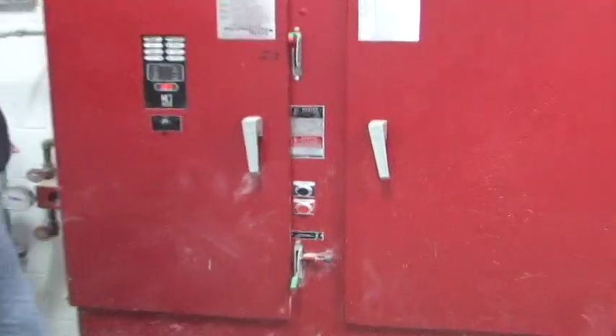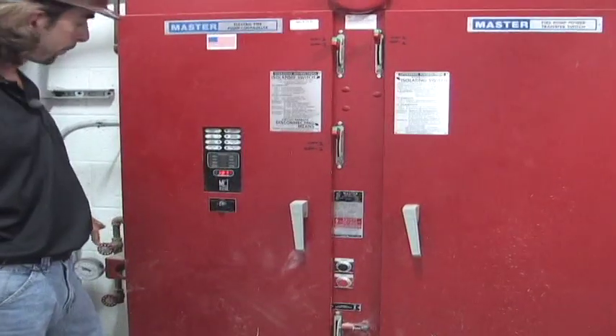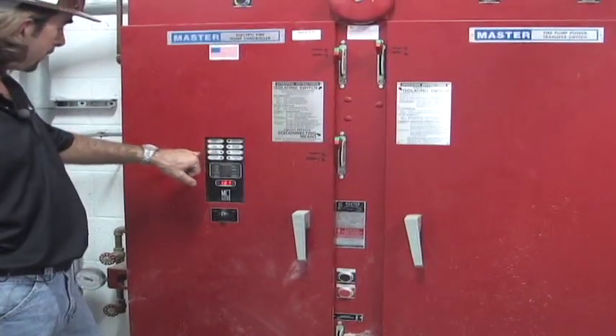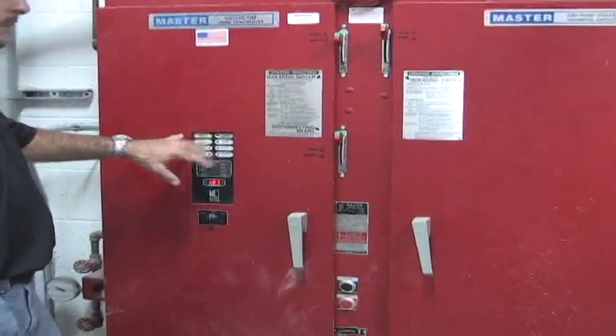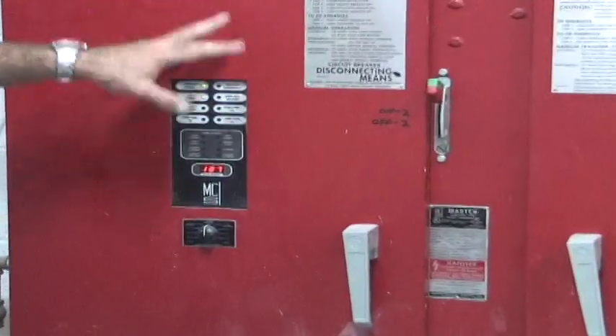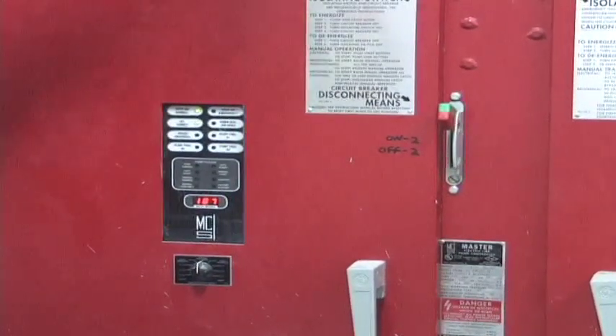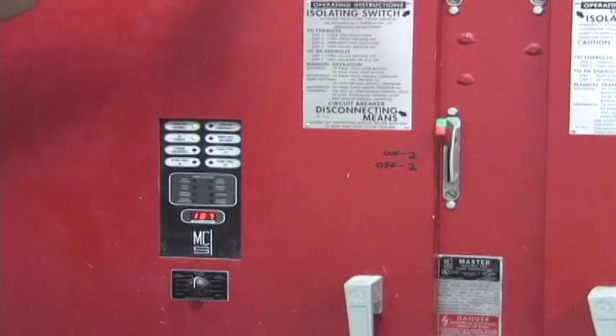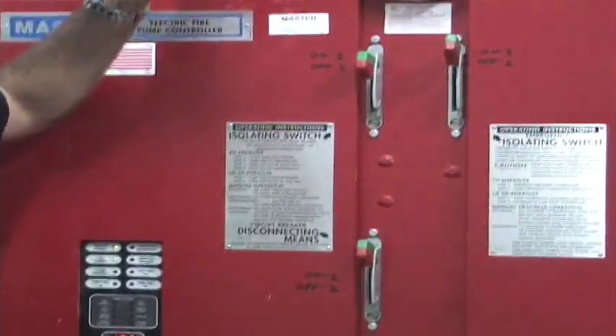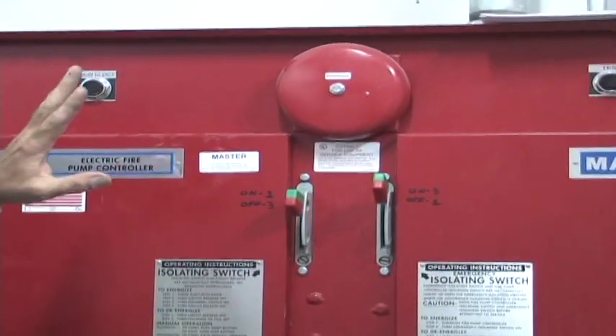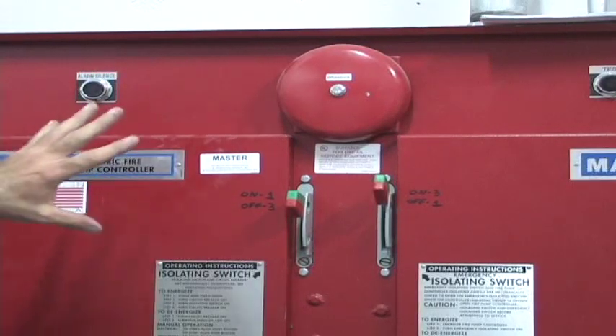Once we get our 150 and we start on a low pressure, we're going to see our fire pump run, start all up. The pump's going to run. Our fire alarm panel is going to show that the fire pump is running. It's going to send a trouble or a supervisory to the alarm panel. You shouldn't get any alarms when this thing runs. All you're going to get is a supervisory.